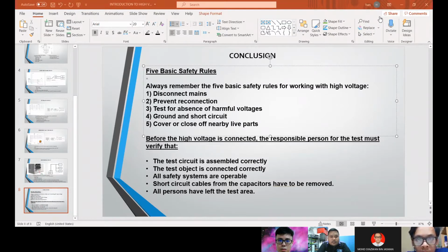Before the high voltage is connected, the responsible person for the test must verify that the test circuit is assembled correctly, the test object is connected correctly, all safety systems are operable, short circuit cables from the capacitor have been removed, and all persons have left the test area.